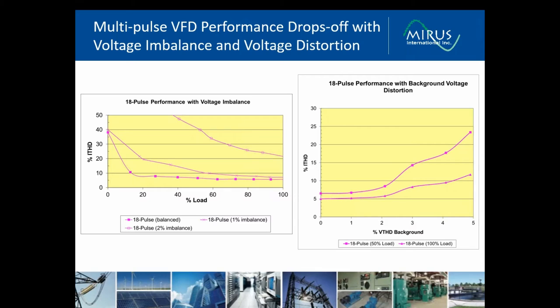These two graphs show the performance of an 18-pulse drive system under various voltage balancing conditions and with background voltage distortion. The first one on the left shows a balanced voltage, and this shows the current distortion of the drive from light load, no load operation, up to full load operation. With balanced voltages, this particular multipulse system performed quite well, with current distortion a little more than 5% at full load, and held that performance reasonably well until we got into light loads. But with just 1% voltage imbalance, you can see the drop-off in performance, still somewhat acceptable.